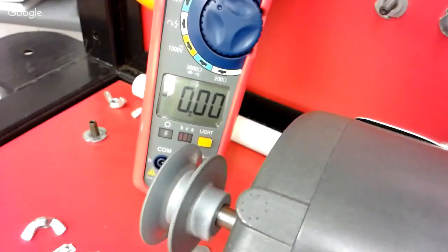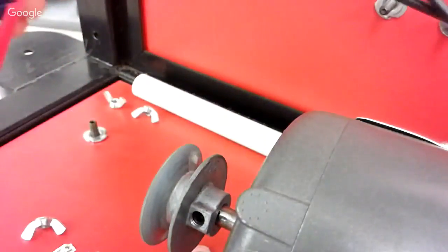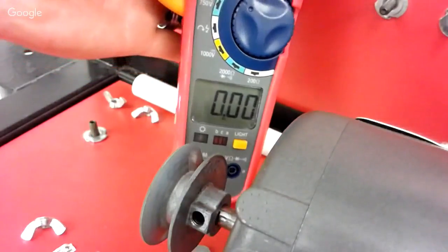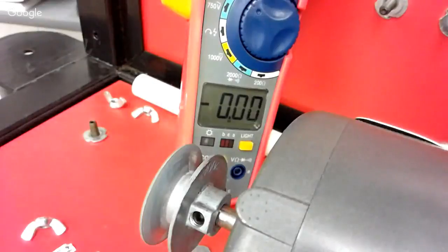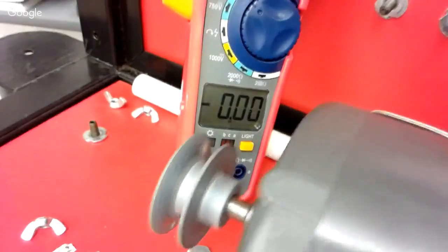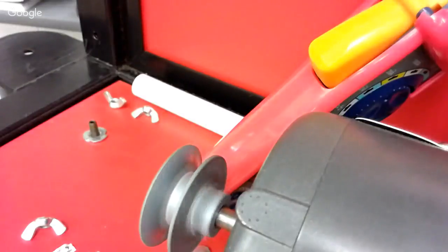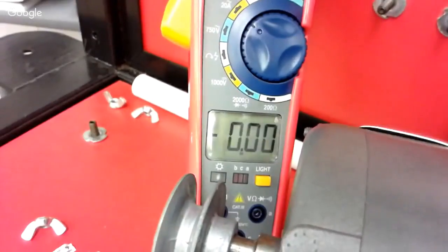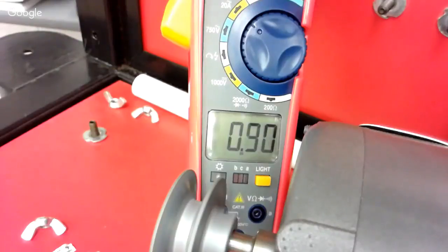So what if I wanted to check all the phases? Well, it's a good idea to make sure it's balanced, that you don't have one phase pulling another, to check all 3 phases on this motor. So you would simply move your wire, clamp on to another wire, and verify each phase is pulling the same amount. If it is not, something's wrong with your motor, more than likely. So we'll go here. Oh, that fell down. We'll see that it is pulling about the same.